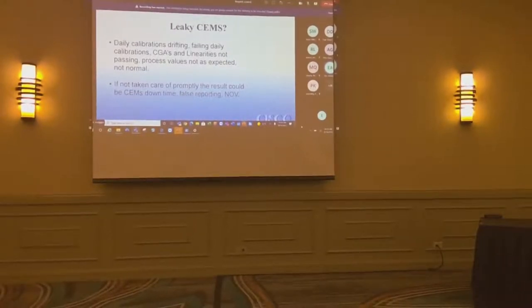But anyway, leaky CEMS. This is a pretty common problem that I get calls on during the weekend and during the week. And actually last week, we spent 2 days troubleshooting the CEMS and replacing analyzers. And the problem was there was a leak. There was a miscommunication or communication problems while troubleshooting.